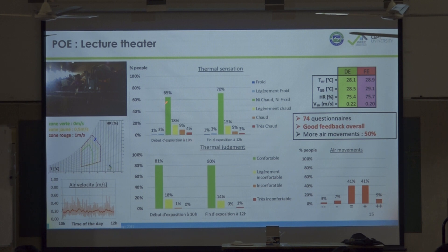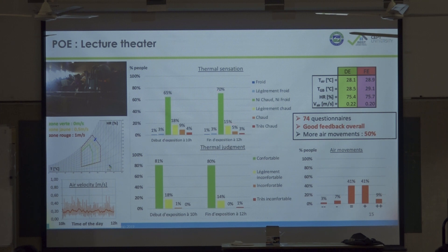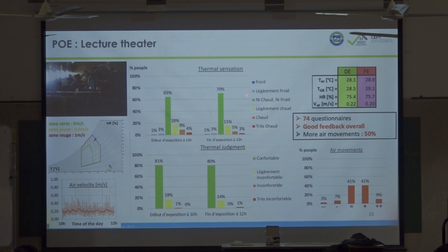Fortunately, the results are positive. For thermal sensation — neutral, slightly warm, warm — at the beginning 60 percent felt neutral, and at the end 70 percent felt neutral plus 15 percent slightly warm. In terms of satisfaction, we need at least 80 percent. So 70 plus 15 equals 85 percent — fortunately above the threshold — though 3 percent felt hot and a few felt very hot.